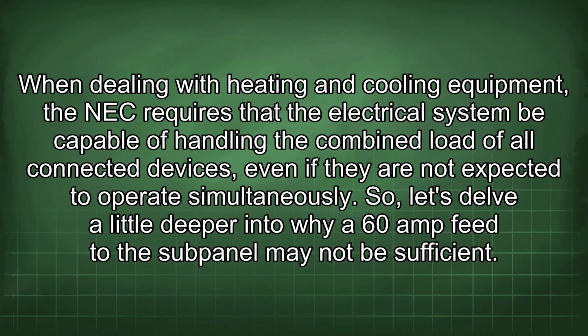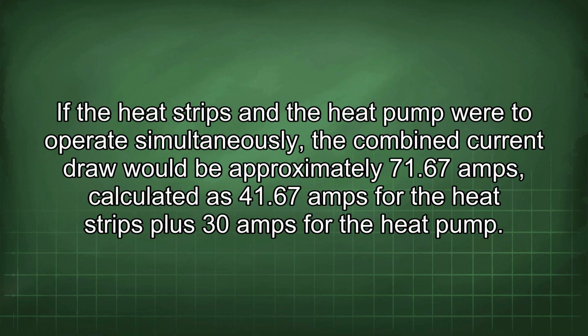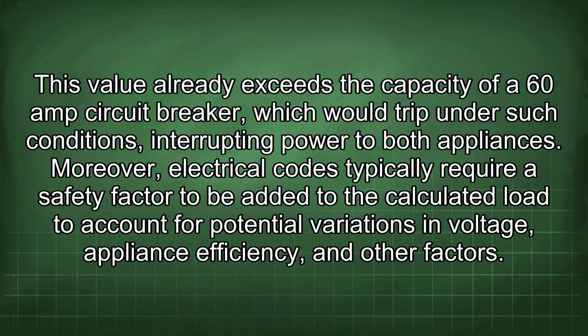So, let's delve a little deeper into why a 60 amp feed to the subpanel may not be sufficient. If the heat strips and the heat pump were to operate simultaneously, the combined current draw would be approximately 71.67 amps, calculated as 41.67 amps for the heat strips plus 30 amps for the heat pump. This value already exceeds the capacity of a 60 amp circuit breaker, which would trip under such conditions, interrupting power to both appliances. Moreover, electrical codes typically require a safety factor to be added to the calculated load to account for potential variations in voltage, appliance efficiency, and other factors.